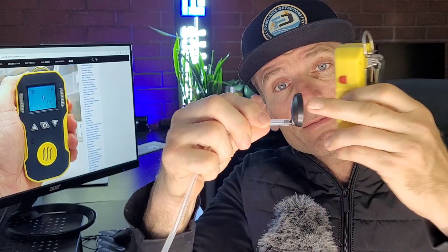Let's do a live demo. I've got a bottle of hydrocarbon styrene right here. I have this calibration cap — it comes with the unit when you purchase it — and it's designed to deliver gas directly onto the sensor from a gas bottle or from a pump. As you can see, we're in clean air, showing zero parts per million. We're going to start delivering gas to the unit; it takes several seconds to start registering. You can see the front display — it has a backlight — and as concentration increases, it's going to trigger the alarms. At 10 parts per million — bang — that's the way it works. It reacts very fast and efficiently to styrene gas.